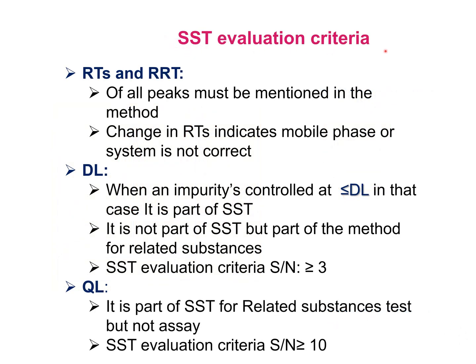SST evaluation criteria: RTs and RRTs of all components must be mentioned in the method. If there is any variation in RTs, it means either there is a problem with the mobile phase or with the system, and hence the same problem must be rectified before analysis is started.